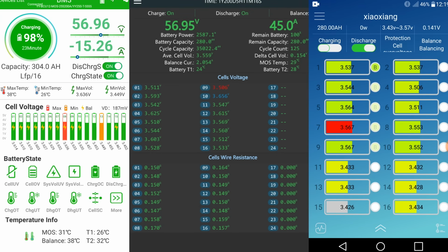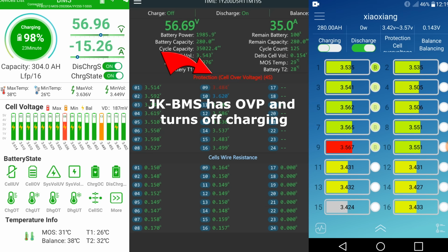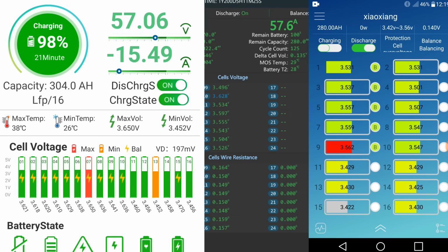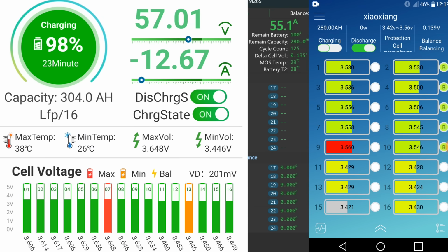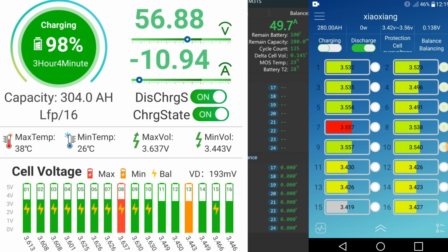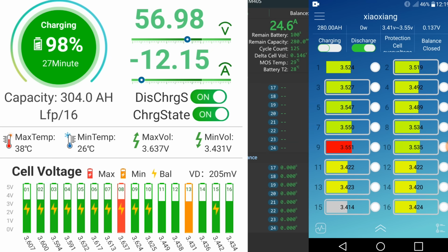While the Heltec BMS in the top shelf battery has not turned off charging, it is still charging with 15 amps. It is balancing at 197, but it will turn off any second - 55 amps into the batteries.